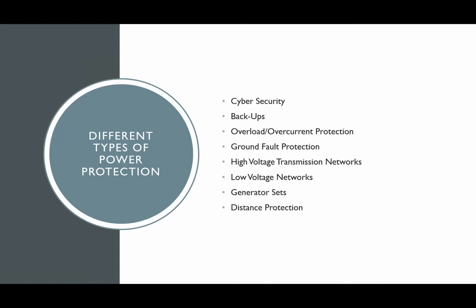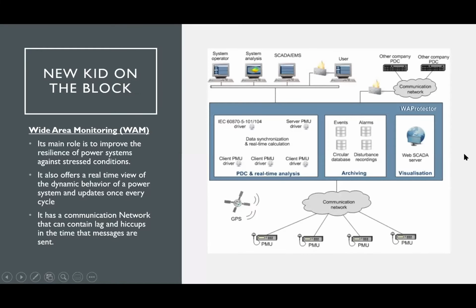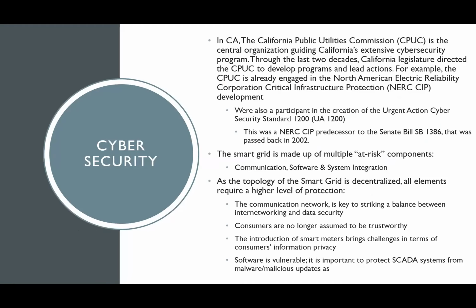Here we have the different types of power protection. We have cybersecurity, backups, overload and overcurrent protection, ground fault protection, high voltage transmission networks, low voltage networks, generator sets, and distance protection. But before we go into that, we'll talk about, as I like to call it, the new kid on the block, which is the new type of protection being talked about, wide area monitoring, also known as WAM. Its main role is to improve the resilience of power systems against stressed conditions. It also offers a real time view of the dynamic behavior of a power system and updates once every cycle. It has a communication network that can contain lag and hiccups in the time that messages are sent. And right here is a picture of what wide area monitoring would look like. And then we'll go over to the ones that are actually being done.